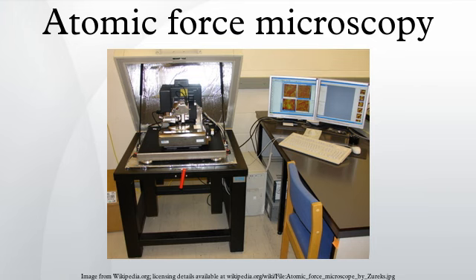If the tip was scanned at a constant height, a risk would exist that the tip collides with the surface, causing damage. Hence, in most cases a feedback mechanism is employed to adjust the tip to sample distance to maintain a constant force between the tip and the sample. Traditionally the tip or sample is mounted on a tripod of 3 piezo crystals, with each responsible for scanning in the X, Y and Z directions.